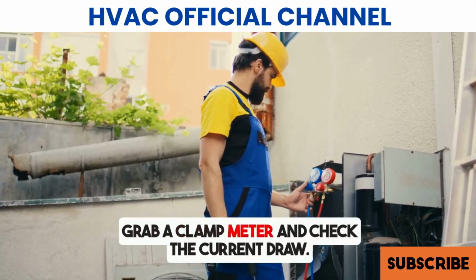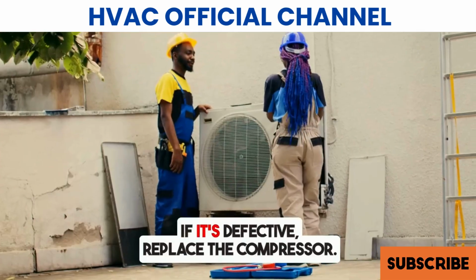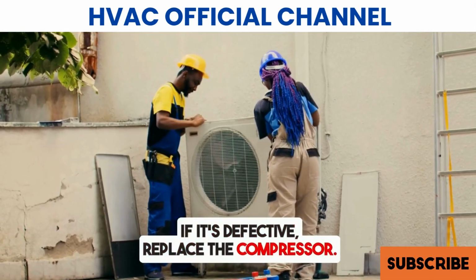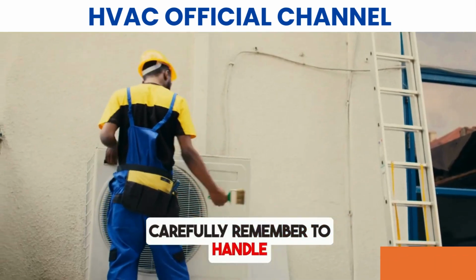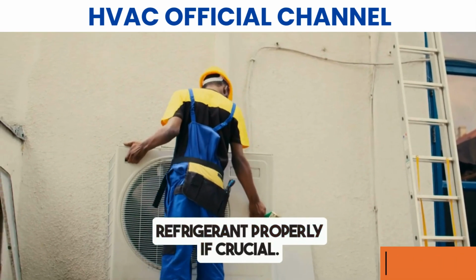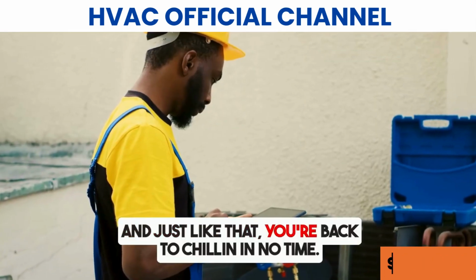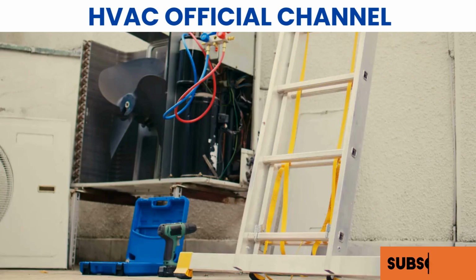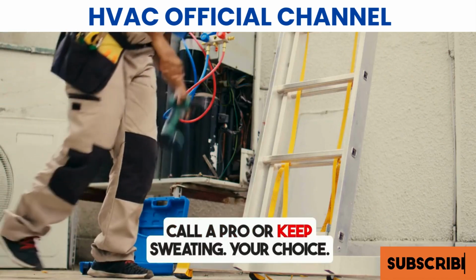Grab a clamp meter and check the current draw. If it's defective, replace the compressor carefully. Remember to handle refrigerant properly. It's crucial. And just like that, you're back to chillin' in no time. Need help? Call a pro or keep sweating.